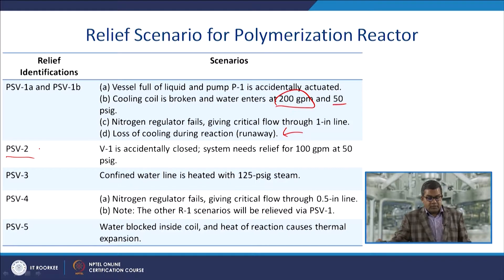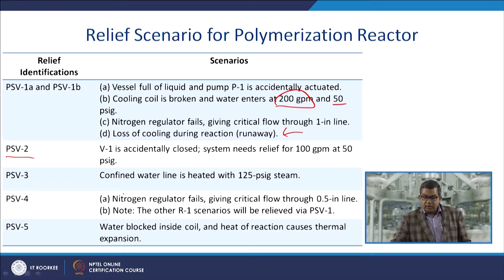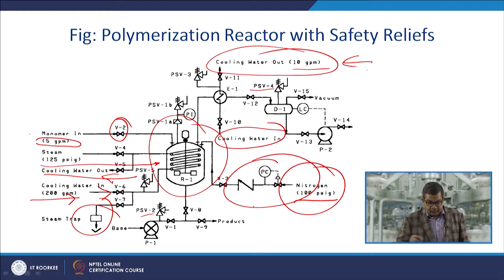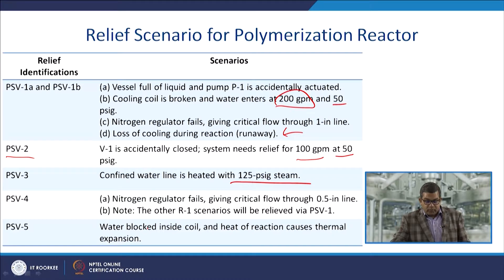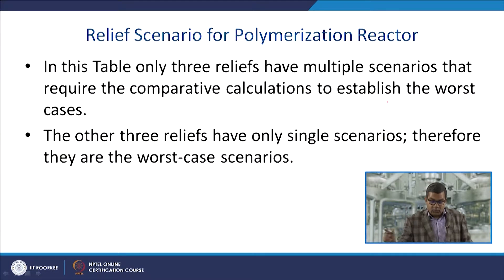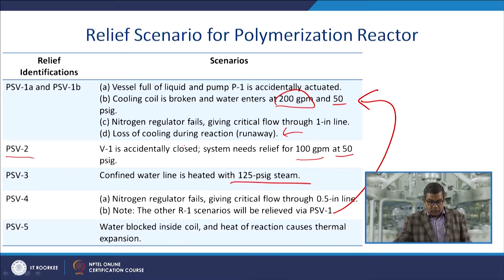Additional scenarios include PSV-2 — valve-1 accidentally closed requiring relief for a specified quantity; PSV-4 — nitrogen regulator failure giving critical flow through a 0.5-inch line; reactor-1 scenario relieved via PSV-1; and PSV-5 — water blocked inside the coil where heat of reaction causes thermal expansion. These represent the full set of relief scenarios for this reactor.